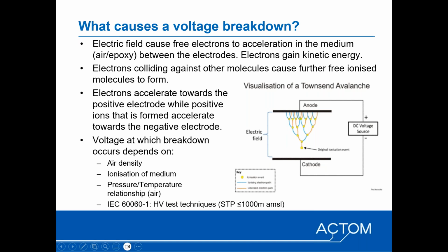The voltage at which breakdown occurs depends on the air density. So if you have a low air density, for instance at high altitudes, the spaces between the molecules are big enough for the electrons to gain enough kinetic energy, so you don't need a high voltage to accelerate the electrons to create a breakdown. At high air densities, for instance at low altitudes, the space between the molecules is very small, and because of the denseness of the air, you don't have enough space for the electrons to gain enough kinetic energy to release electrons.